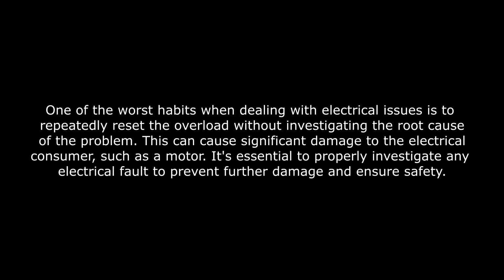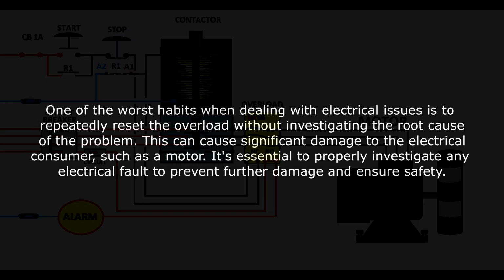Now let's talk about people's habits. People like to reset the overload without investigating the motor. Sometimes the motor might run a couple of days because there could be different types of faults, electrical faults, mechanical faults, bearings, etc. And they just constantly reset the overload until the motor is completely damaged, or the wire is burned, or anything. So that's not recommended.